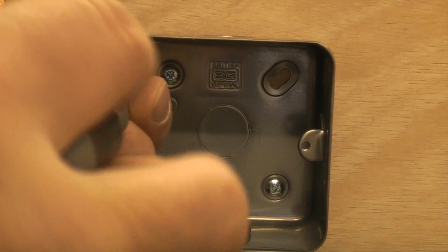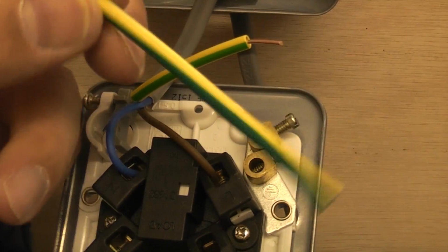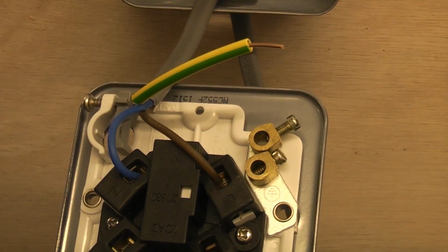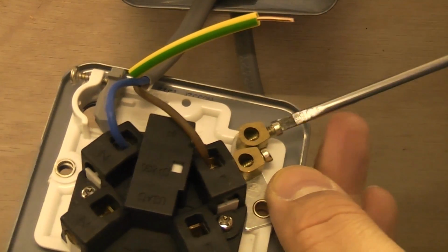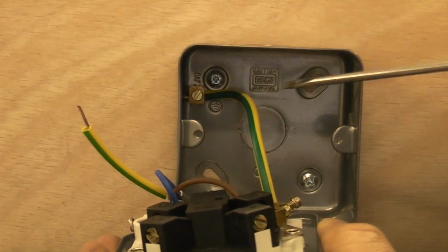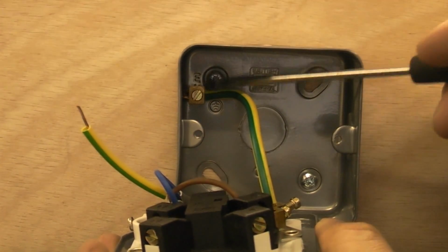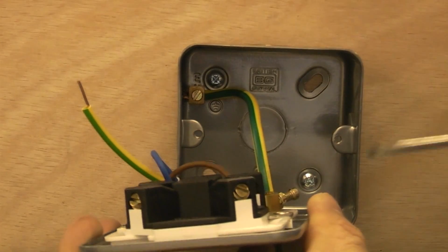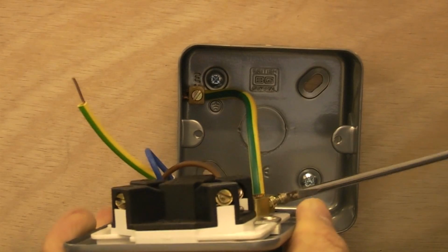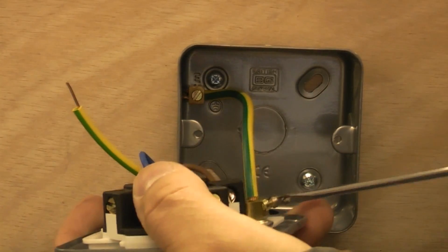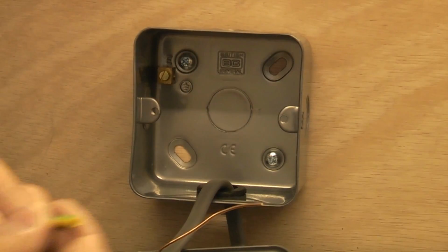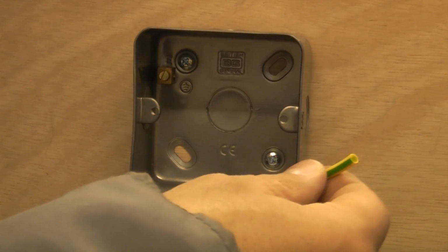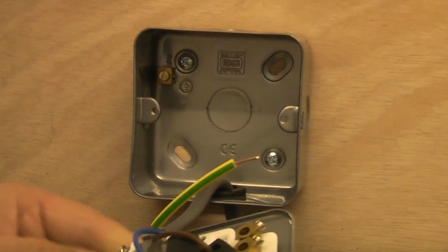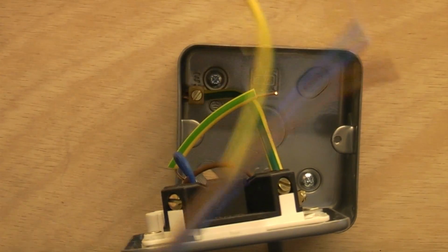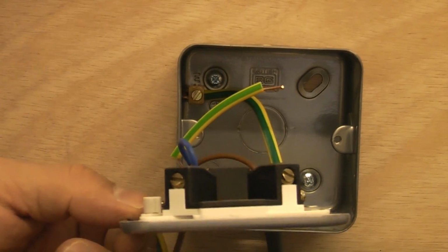We're now going to undo the earthing terminal in the back box. And then I'm going to get a piece of earthing wire, which has got a copper conductor in it. And then I'm going to undo the earthing terminal. I've now put a piece of earthing wire to the earthing lug on the back box, and that also connects to the FCU. We now just need to tighten that up. I'm then going to cut a piece of earth sleeving that will slide onto the earth wire to identify it as being the earth.